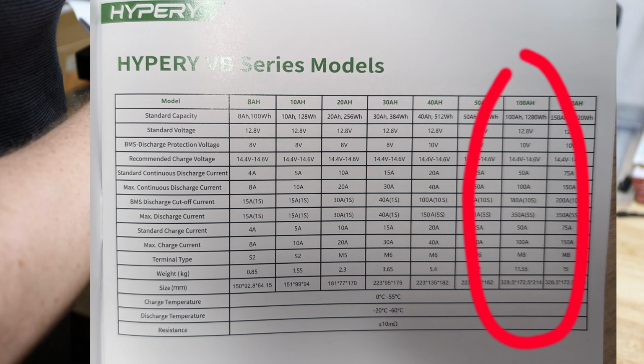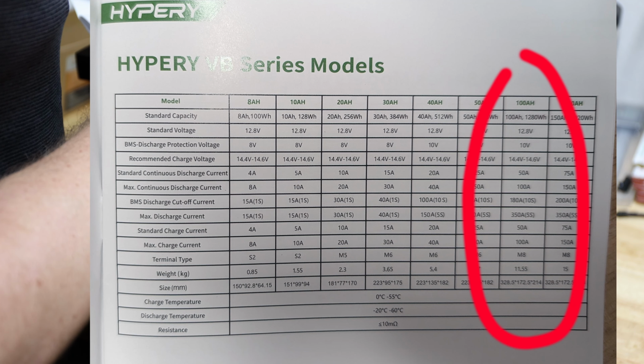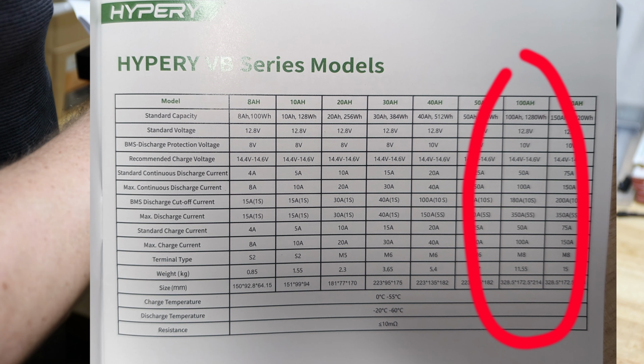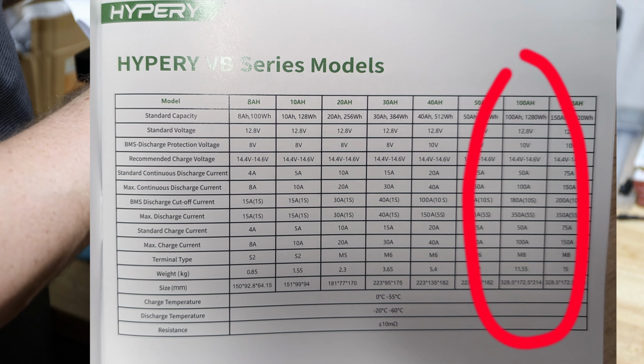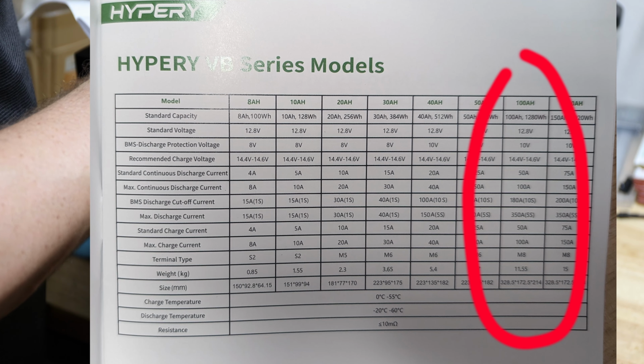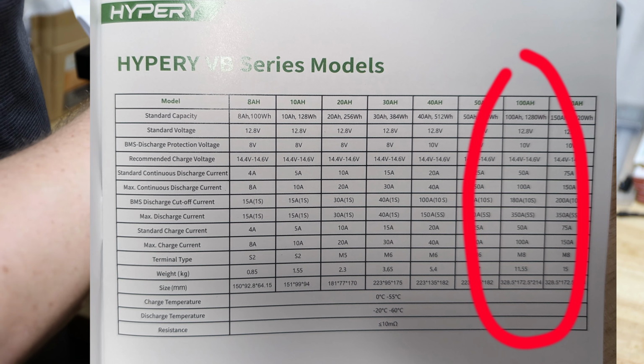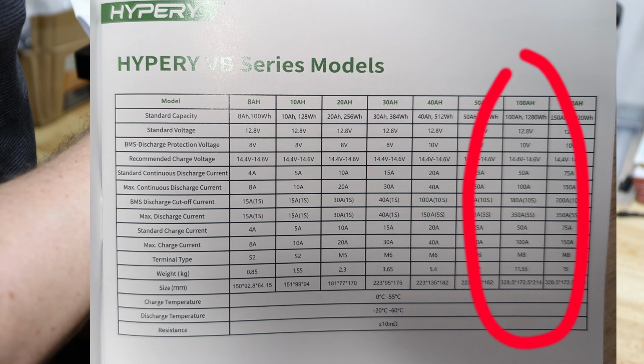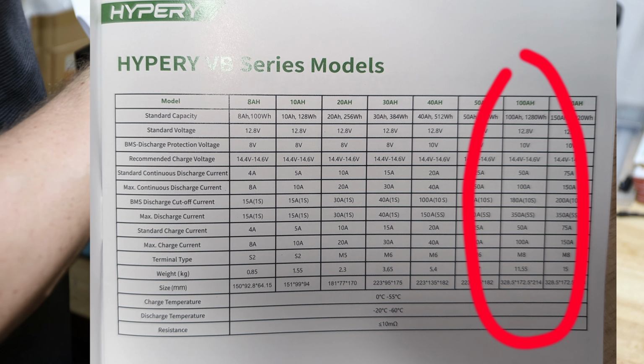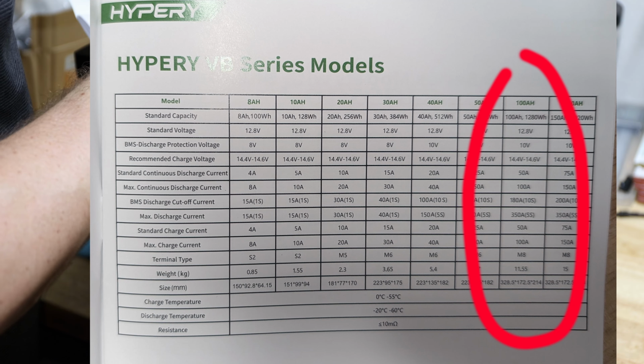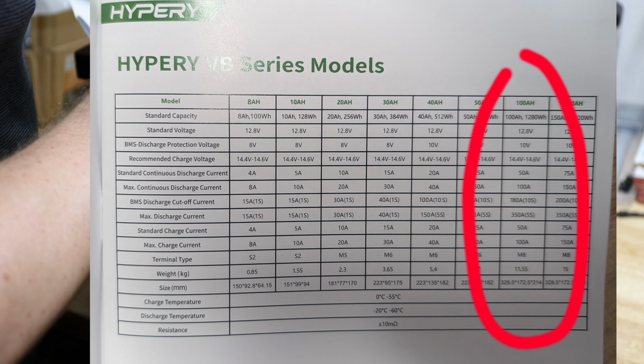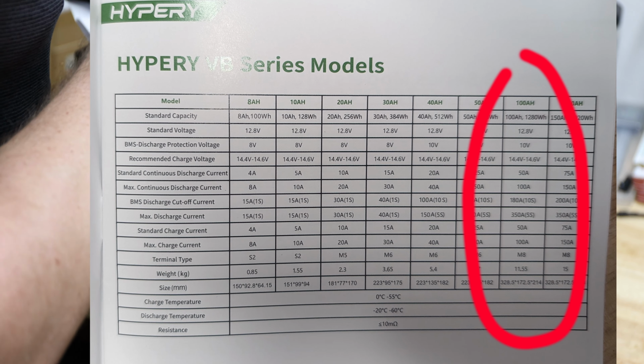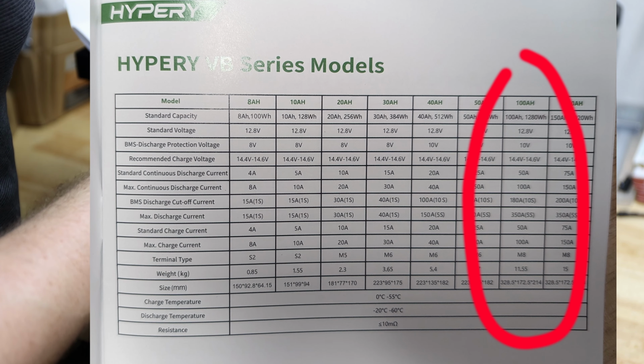We do have a standard continuous discharge current of 50 and a max continuous discharge current of 100 amps, so pretty standard values. Then we have the BMS discharge cutoff current, which is at 180 amps for 10 seconds, and max discharge current is 350 amps. Oh, that is a high number. I don't think I have enough power to pull this from the battery to test it. We'll see. And then we have a standard charge current of 50, as well as a max charge current of 100 amps. And yeah, M8 bolt.